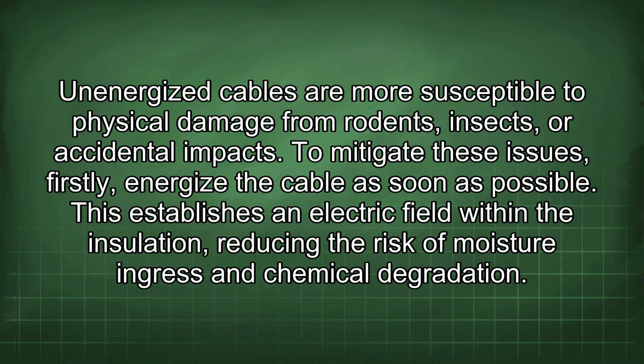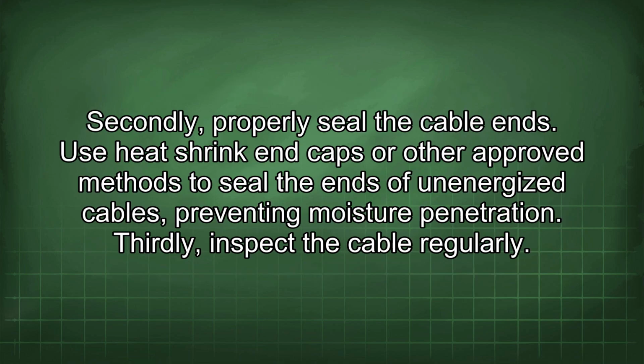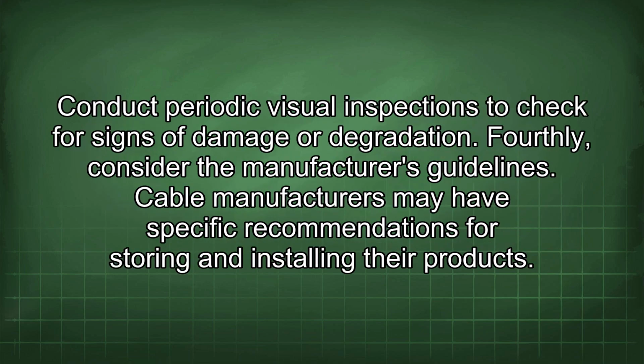To mitigate these issues, firstly, energize the cable as soon as possible. This establishes an electric field within the insulation, reducing the risk of moisture ingress and chemical degradation. Secondly, properly seal the cable ends. Use heat shrink end caps or other approved methods to seal the ends of unenergized cables, preventing moisture penetration. Thirdly, inspect the cable regularly. Conduct periodic visual inspections to check for signs of damage or degradation.